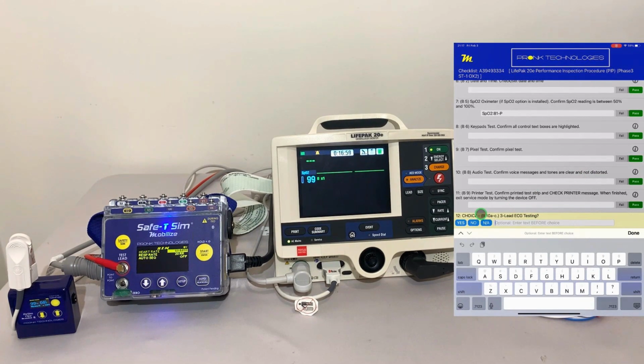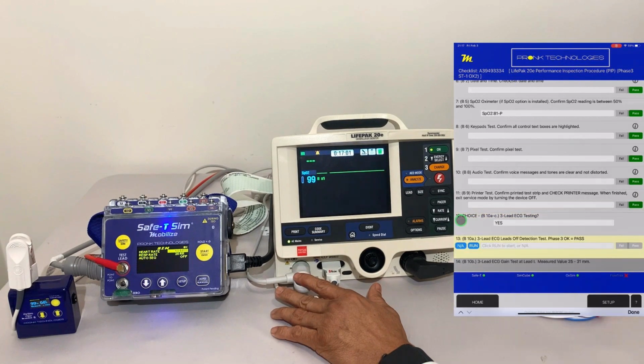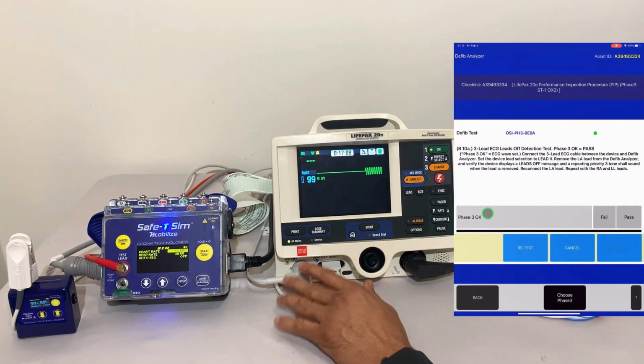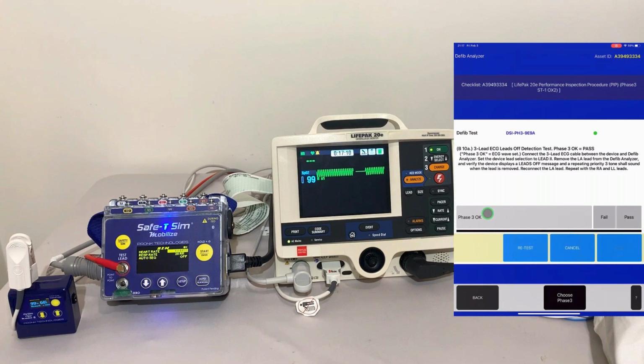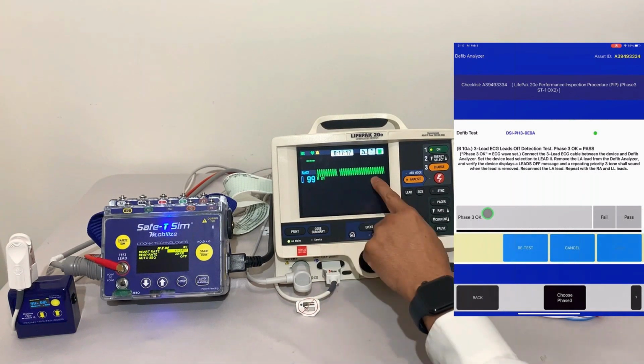In this case, we're going to select yes. And now it wants us to do a leads off detection test, so we're going to hit run. The defib analyzer is now going to be generating a sine wave, which will be picked up and transmitted through the ECG leads that are connected to the defibrillator. We can see the sine wave appearing here.